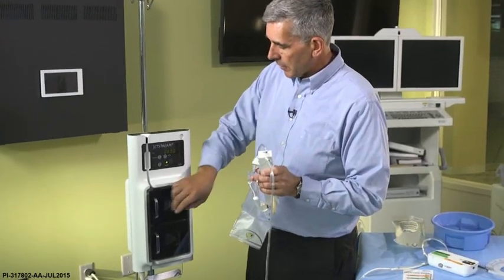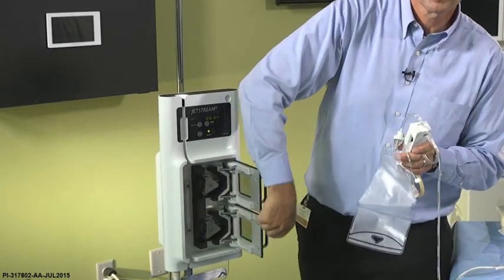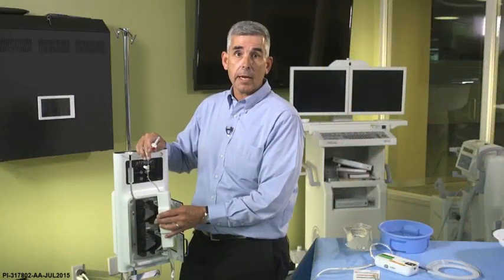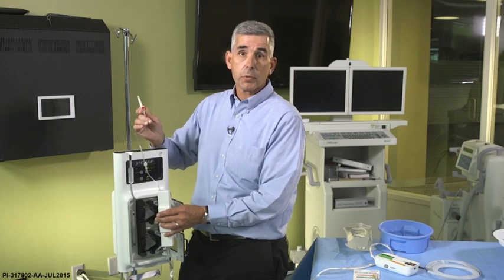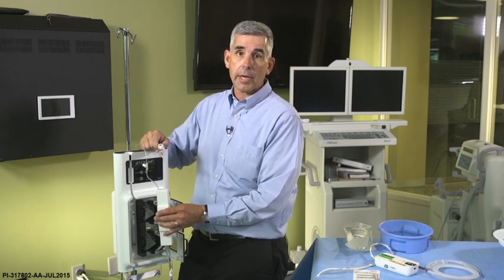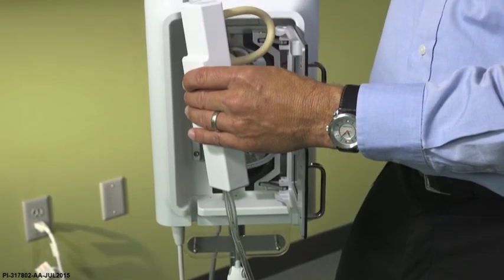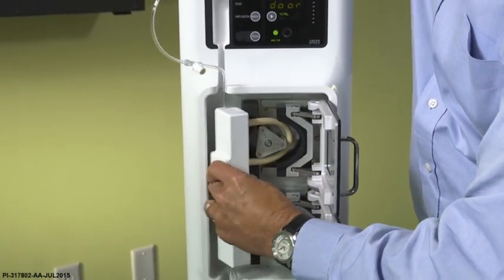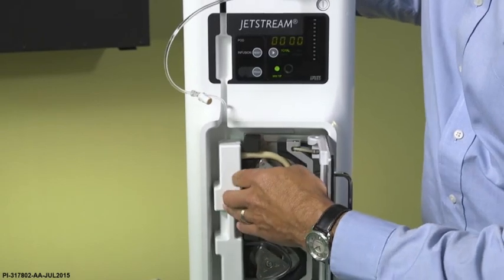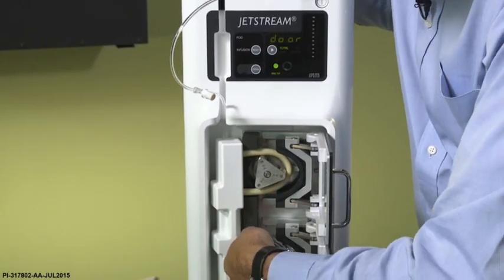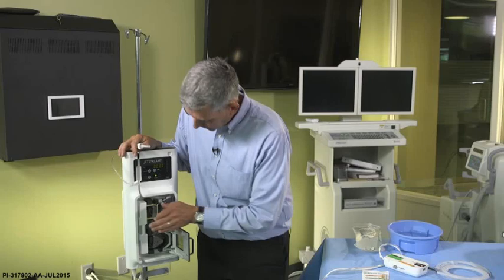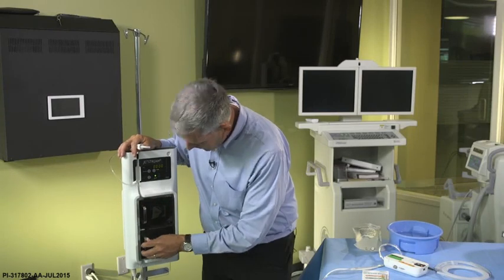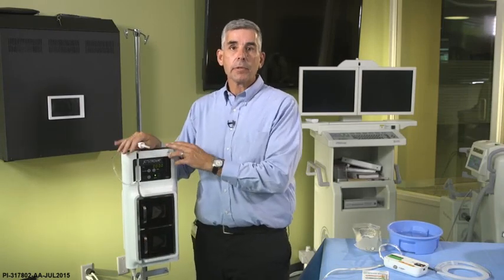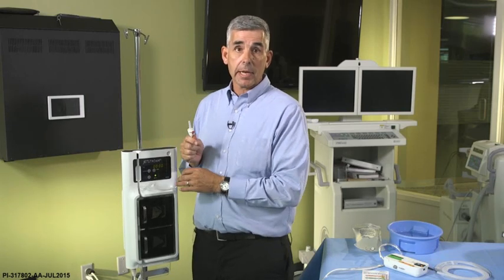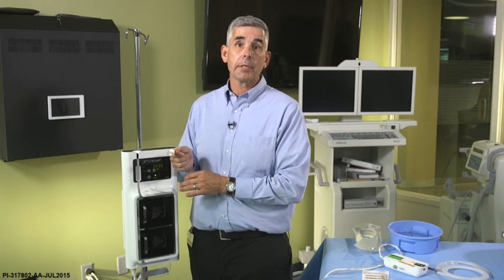First, we'll open the doors on the console. Taking the baton, we will load the baton into the console. The IV spike will be towards the top with the waste bag and other connectors hanging below. Taking the baton, you will place it in the console, aligning the tubings around each roller pump. Make sure that the tubing is seated properly around each roller pump before closing the doors. We will now take the IV tubing and place it through the bubble detector channel, making sure to seat the tubing to the back of the channel, and then we'll spike the saline.